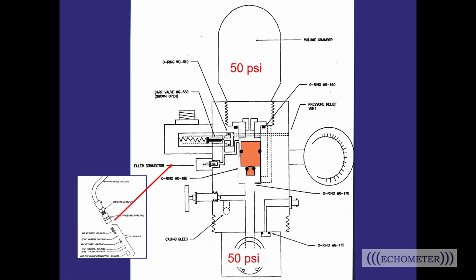Okay. Right, so even the order can mess it up. Yes, please go ahead. Just even the order can cause it to be a problem. So if you lose one or they're out of order, it'll cause it to leak, and you may not expect it to be leaking, even though all the parts are there. Right, so that's another reason why it's really important to have your schematics there, just to make sure that you're getting everything put back together in the same order. Same thing with the solenoid and the plunger. There's tons of parts in there.